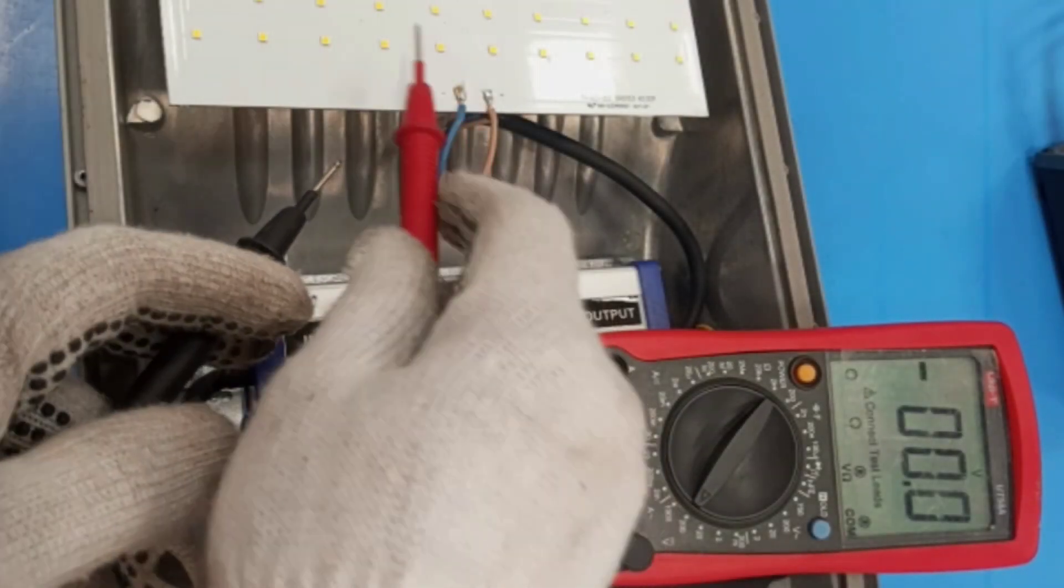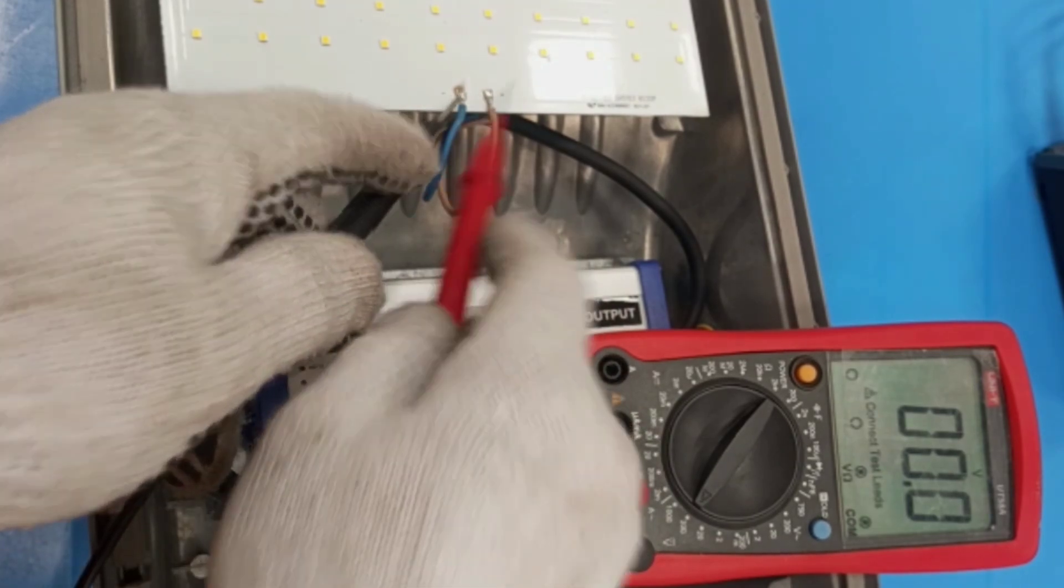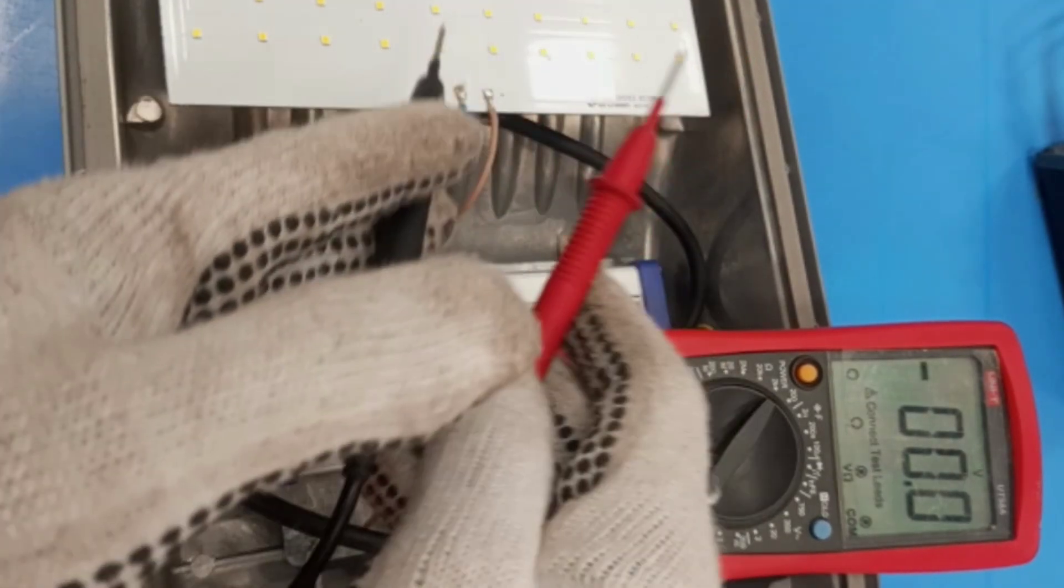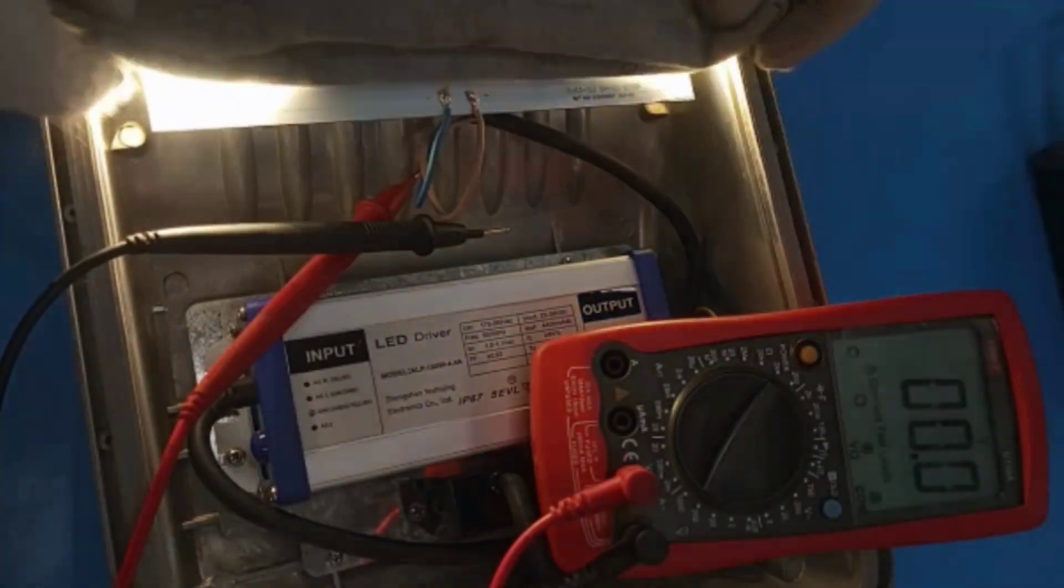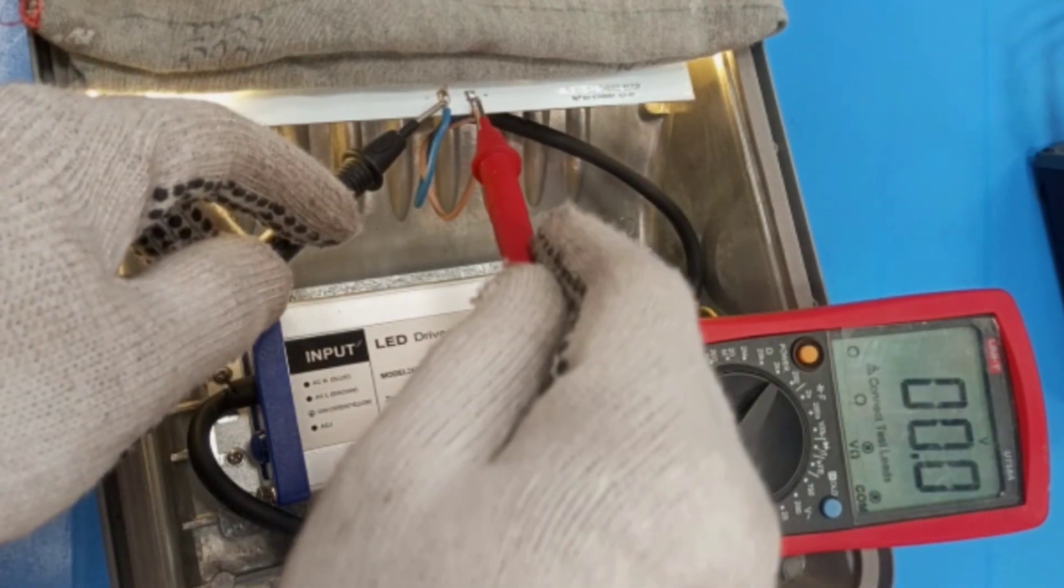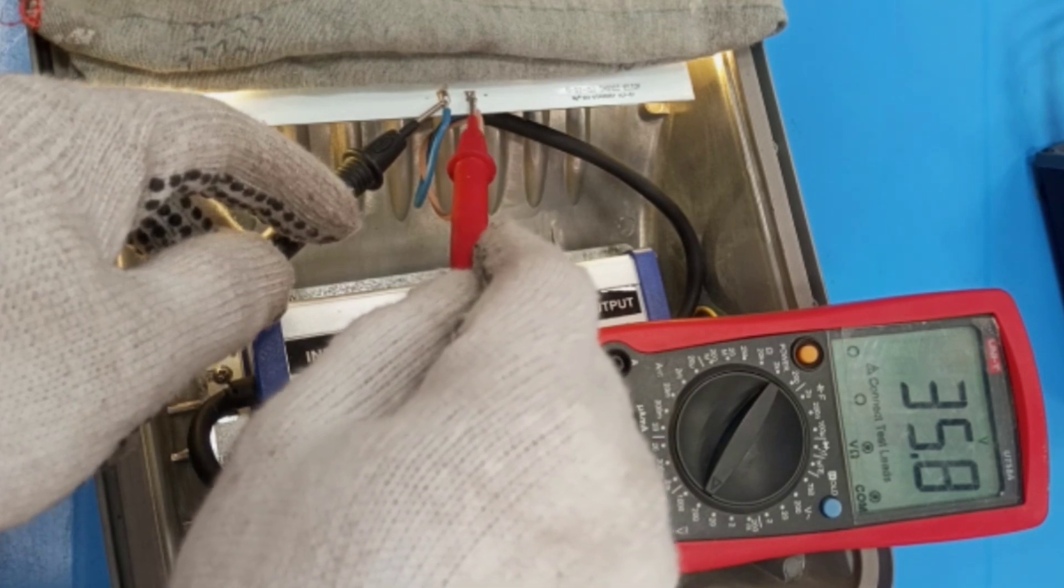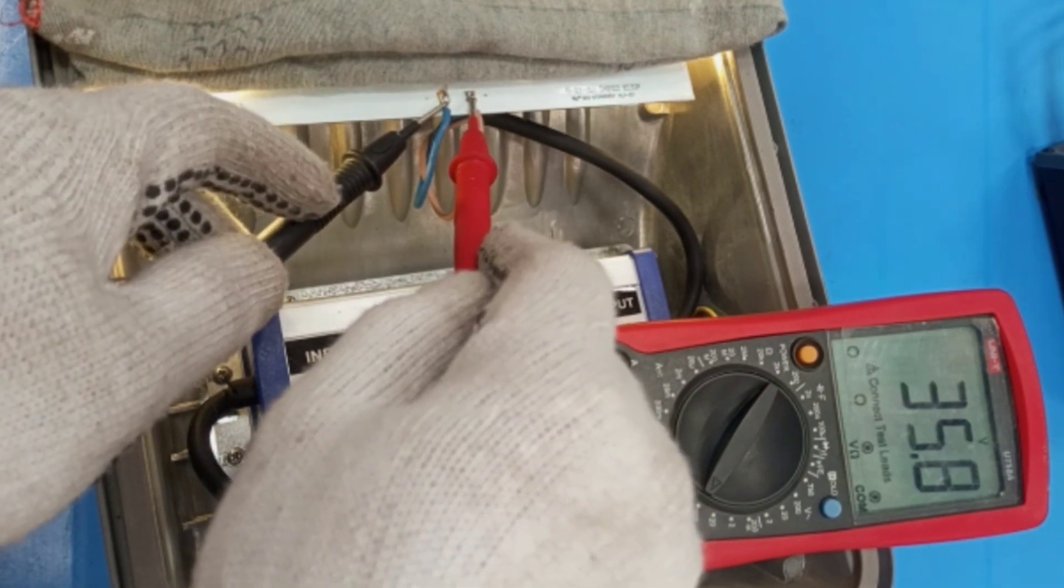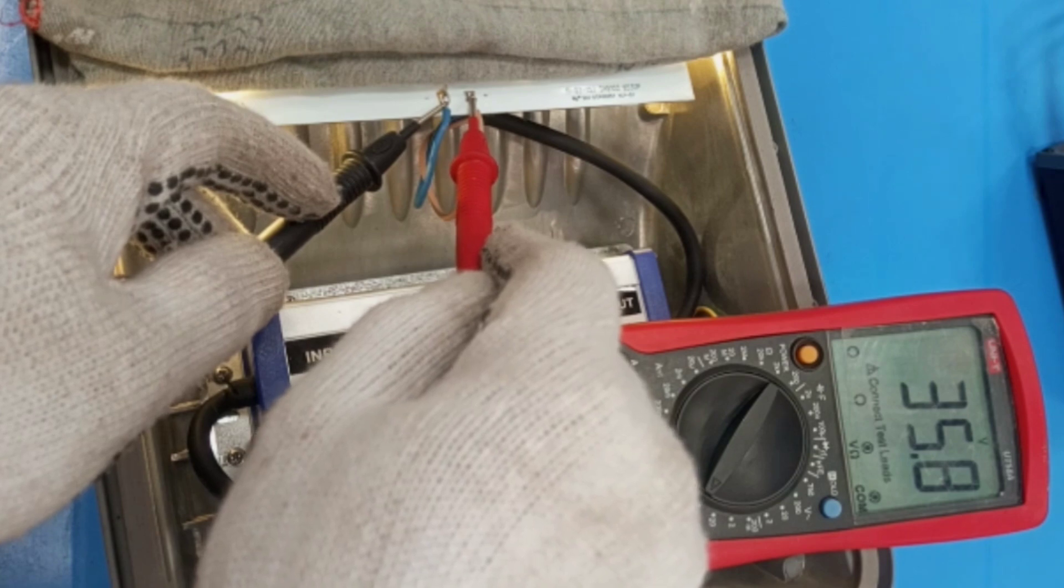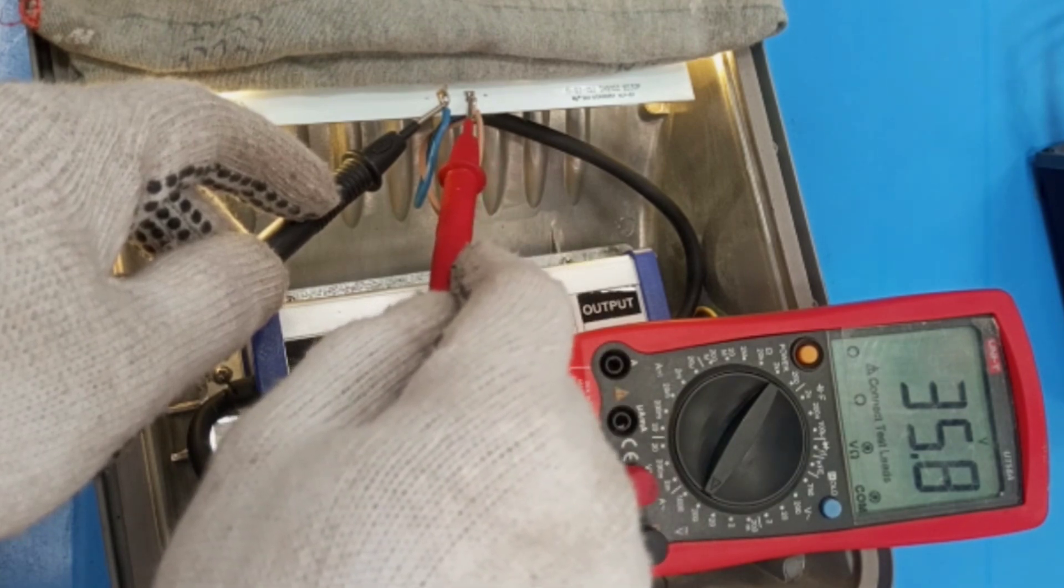This is the output to the LED module. I'm going to measure the voltage across these two lines. Before I can do that, I have to switch the lamp on. So I use the black lead to the blue wire, which is neutral, and then here. The DC output voltage to the lamp is 35.8 volts.